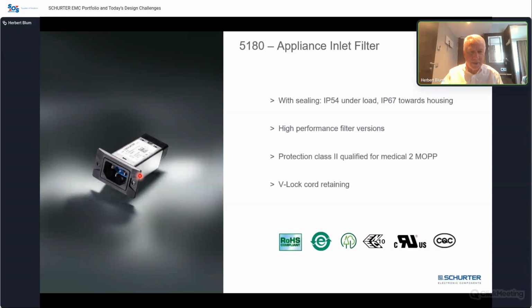This 5180 is, let's say, our newest inlet filter that we brought to the market last year. It's completely sealed all around, IP67 and IP54 for the cord connection. It is class 1 or class 2. Class 2 is also qualified for medical 2 MOPP. This is, according to medical standard, 2 means of patient protection.